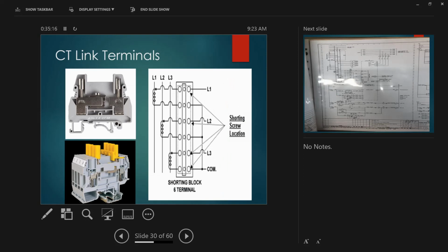CT-Link, that's what I mentioned earlier, is where we do our testing. We put our banana plug here and inject into the relay. Sometimes people forgot to restore it properly, and you will have an open circuit relay. If the switchboard is energized, there will be a high induced voltage in this area because you opened the CT, and you will end up burning this and burning the CT as well. So this one should be restored properly. That's why we normally take photos as found and as left, so that we can make sure that everything is restored properly. An open CT will cause high induced voltage in the secondary.